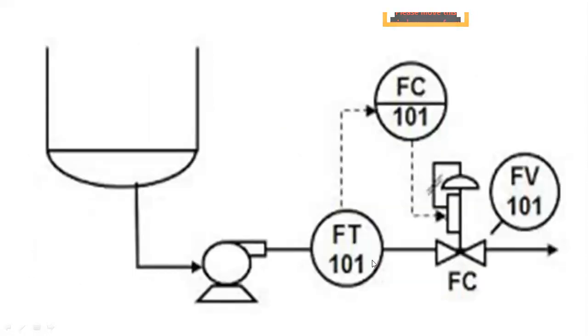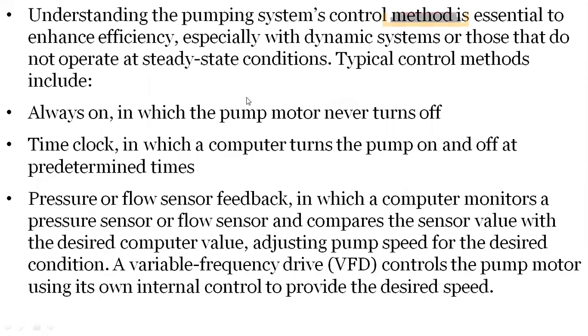For typical pump control, you have a flow transducer feeding a flow controller which operates a flow control valve. Understanding pumping system control methods is essential to enhance efficiency, especially in dynamic systems that do not operate at steady-state conditions. Typical control methods include: always-on (motor never turns off); time-clock control (computer turns pump on and off at predetermined times); pressure or flow sensor feedback (computer monitors sensor and adjusts pump speed); and variable frequency drive (VFD), which controls motor speed — more speed means more pumping, less speed means less.